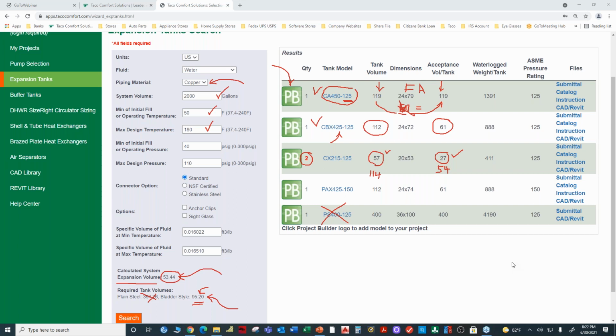And the reasoning behind that is that you could pick a lower temperature than that. If you're using glycol, remember, we're in our very simplified system, we're just using water for our discussion. But if you're using glycol, you could have a much lower temperature if you wanted to start it that way. But it's whatever the lowest temperature is you think is going to be in your system, that would be the point at which you would start.